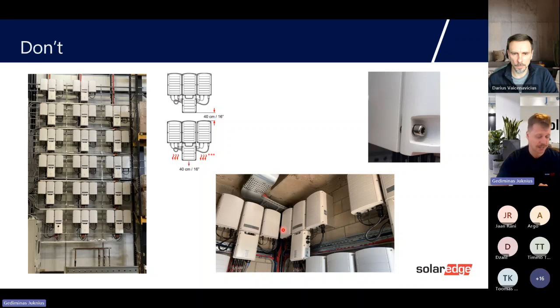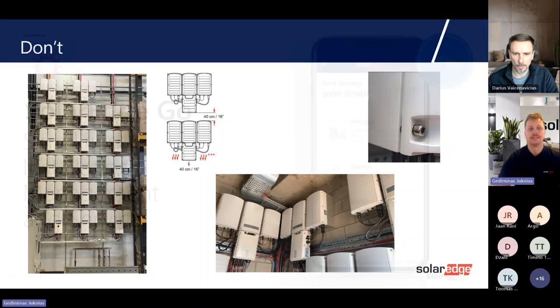What happens when inverters are reaching the temperature limits? They are reducing active power, and that means you're losing production. And we have sites which were not producing well just because it was way too hot in the room. They had to install either AC or ventilation or change the layout of the inverters. There are specific tables which tell you how much heat every inverter gives at its nominal power. Right on Google, the first document that will appear is from the SolarEdge Knowledge Center, and you will see it.